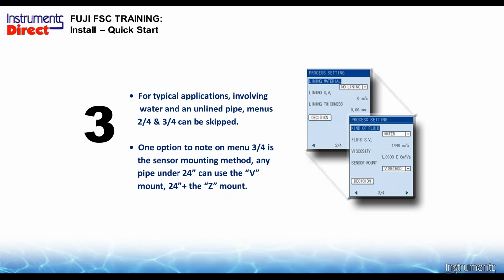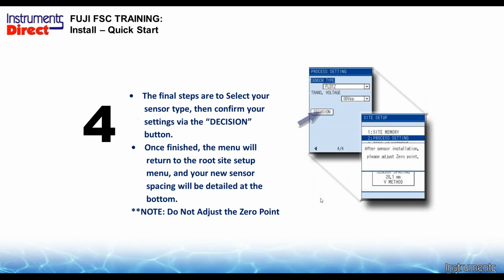The sensor mount, most of you will use the V mount. We said we use that usually from 1/2 inch to 24 inches. If you want to go to the Z mount, you would press the down arrow and pull the next one up. So now, when you're all done, well, the next step I almost forgot, you select the type of transducer. I remember there's a drop-down menu there of all the different flavors of transducer.